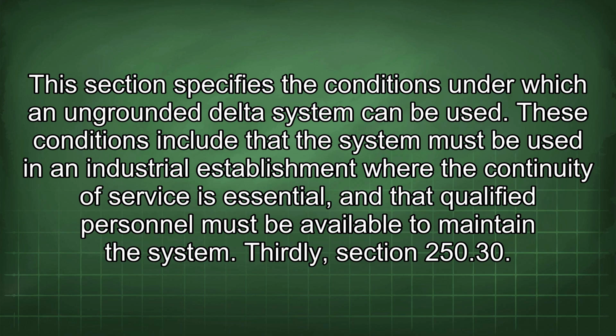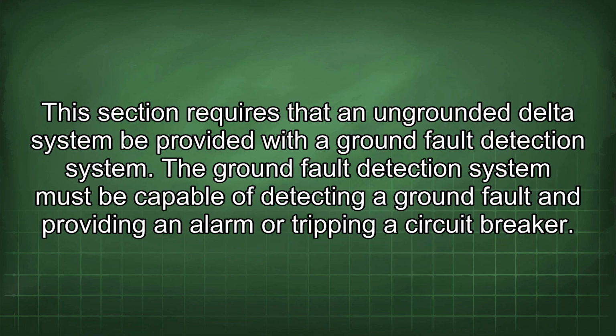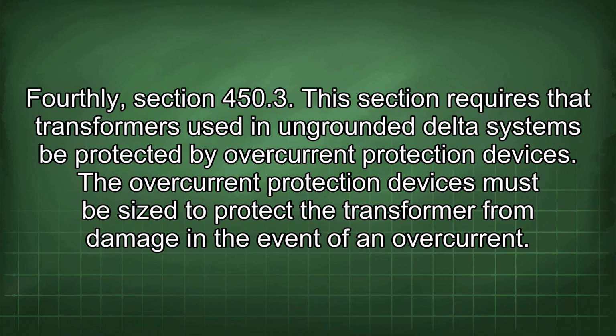Thirdly, Section 250.30. This section requires that an ungrounded delta system be provided with a ground fault detection system. The ground fault detection system must be capable of detecting a ground fault and providing an alarm or tripping a circuit breaker. Fourthly, Section 450.3. This section requires that transformers used in ungrounded delta systems be protected by overcurrent protection devices. The overcurrent protection devices must be sized to protect the transformer from damage in the event of an overcurrent.